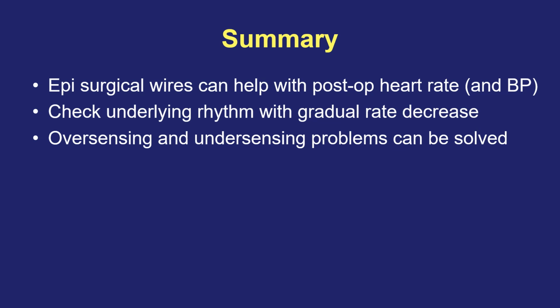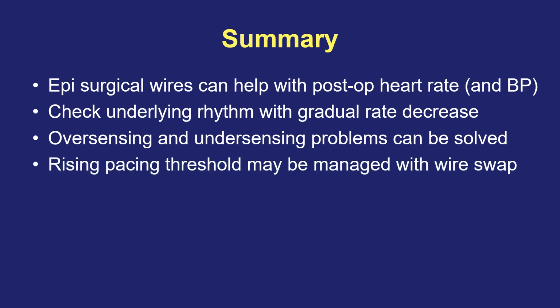Oversensing and undersensing problems can be solved by adjusting either the pacing mode or the sensitivity, in particular in the ventricular channel, making sure that it is seeing true QRS complexes and not pacing on T waves because it missed the QRS, but also not inhibiting pacing inappropriately when QRSs aren't occurring. And so you can tweak that sensitivity dial or number digitally while watching the telemetry and the little flashing light to make sure that it is in fact sensing the native QRS complexes. A rising pacing threshold can be troubleshot by swapping the wires, the anode and the cathode, or finding the better wire and using something else as an anode, either an atrial wire or a skin electrode.